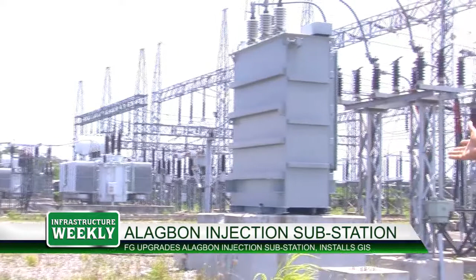He added that the new work has ensured the station is no longer restricted in its operation, but is now a versatile and efficient transmission station. This is one of the new transformers added to the station. It ensures we get maximum supply from the Aja sub-region, where we get 330 kV supply to this transformer. With this, we now have enough load for the other 132 kV transformers. We are no longer restricted in terms of the supply we have here.